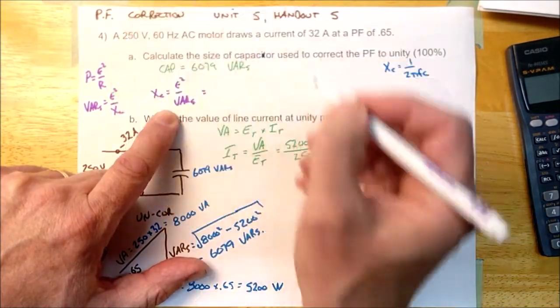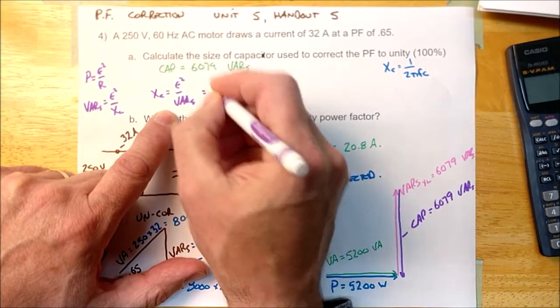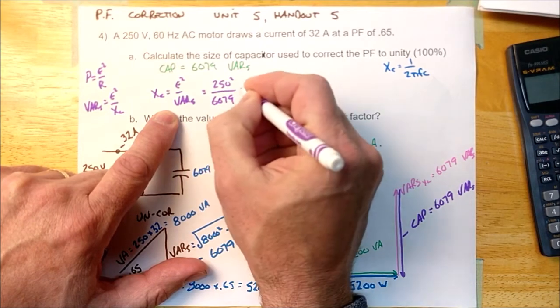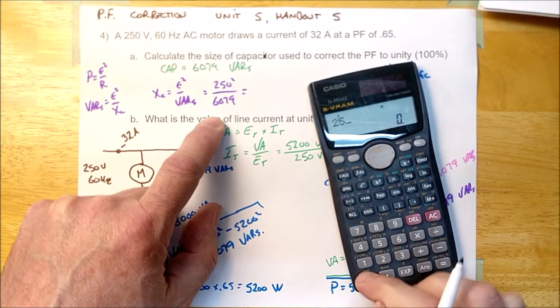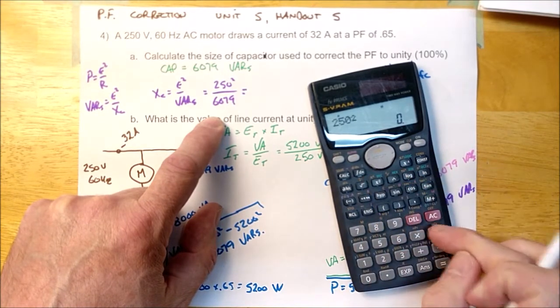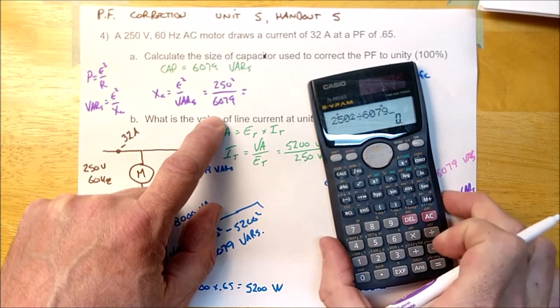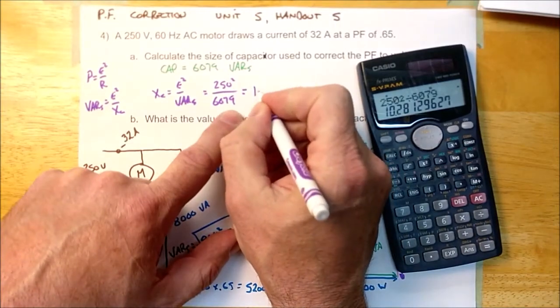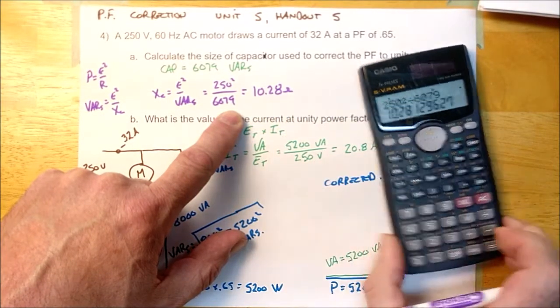Now E squared, 250. VARs is the size of the capacitor. And we're going to calculate that. 250 squared divided by 6079. Yes equals. So this capacitor is 10 ohms, 10.28 ohms.